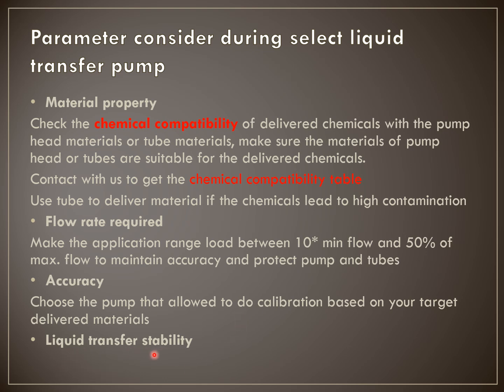The last parameter to consider is stability, which is related to the quality of your device. Most importantly, you also need to consider pressure — most users may not pay attention to this because most liquids are transferred under atmosphere. However, in some types of reactions, pressure may be involved, so you must consider the maximum pressure your pump can provide to ensure the liquid can be delivered into your system properly.